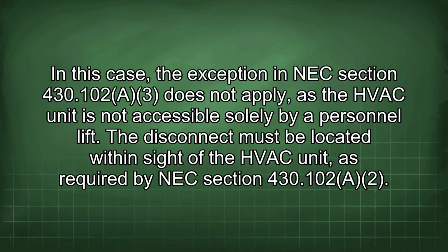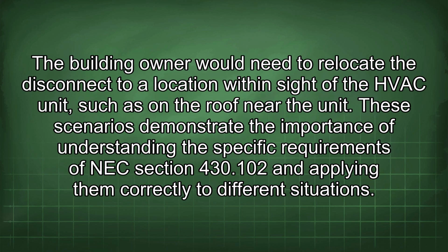In this case, the exception in NEC Section 430.102 A3 does not apply, as the HVAC unit is not accessible solely by a personnel lift. The disconnect must be located within sight of the HVAC unit as required by NEC Section 430.102 A2. The building owner would need to relocate the disconnect to a location within sight of the HVAC unit, such as on the roof near the unit.